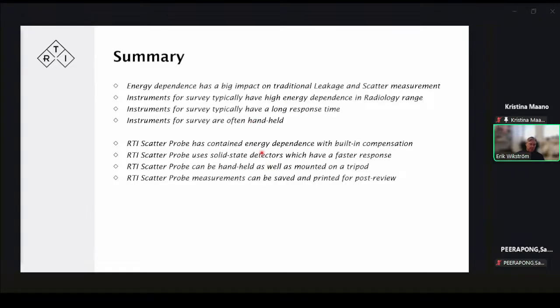So what we offer, and what we've talked about today, is the scatter probe with the compensation for the energy dependence built into the firmware, with the fast response of solid state detectors, mountable on a tripod or handheld. So when you're doing a survey looking for leakage or weak leakage spots around a tube or in the door or wherever, you have those 2 options. It's connected to software where you can save and print the measurement data for review and comparison later on.